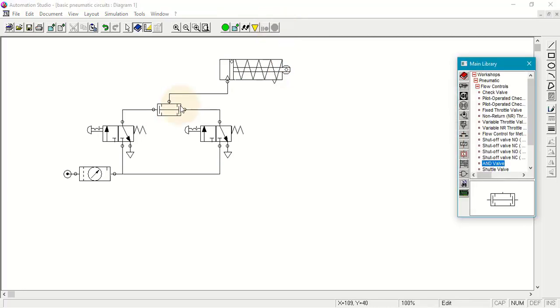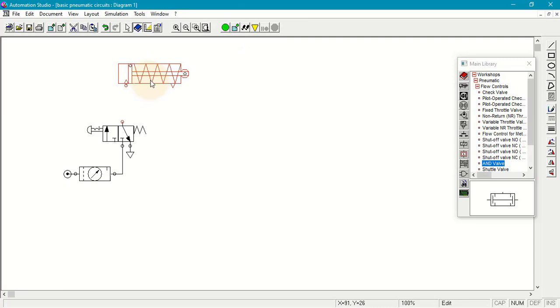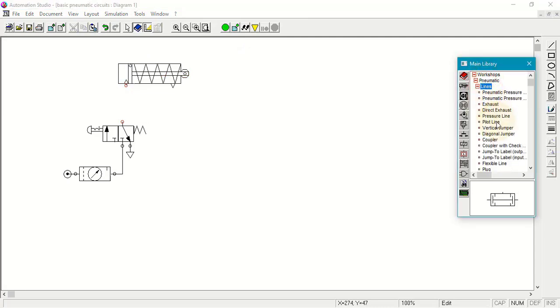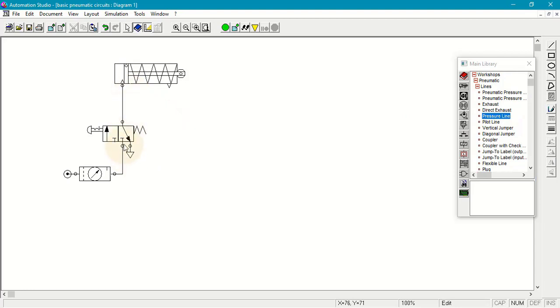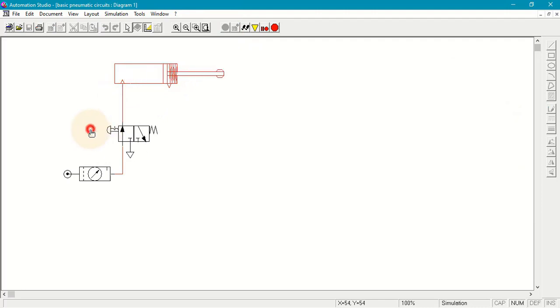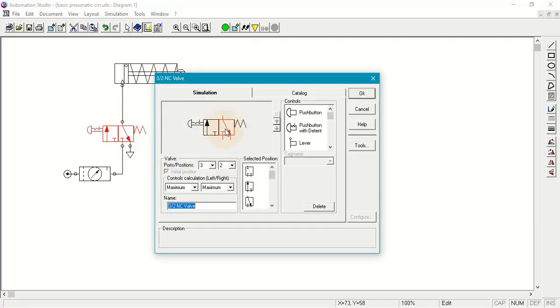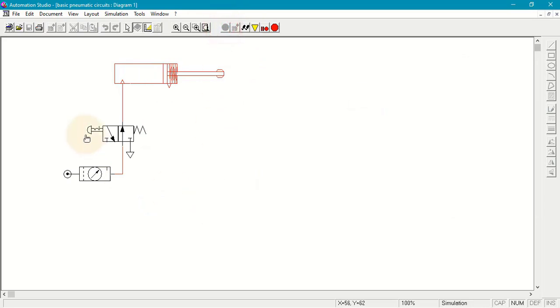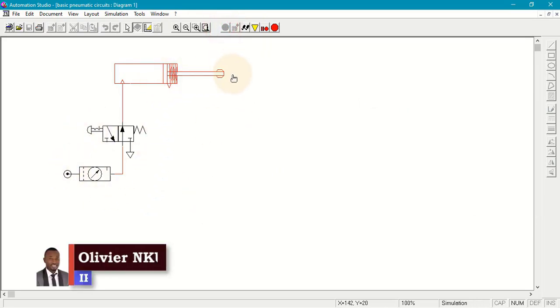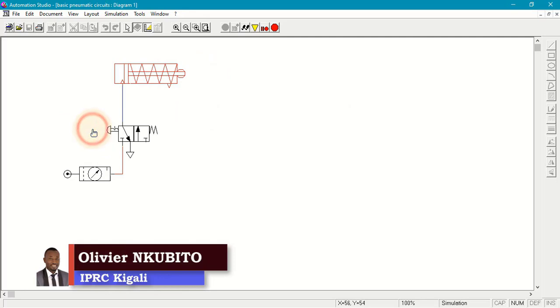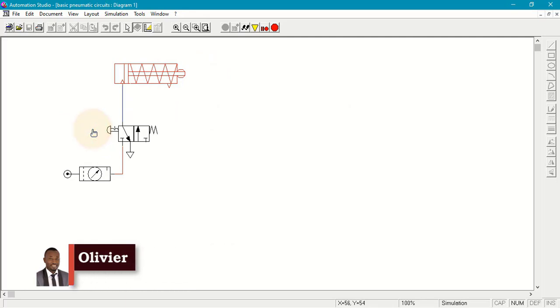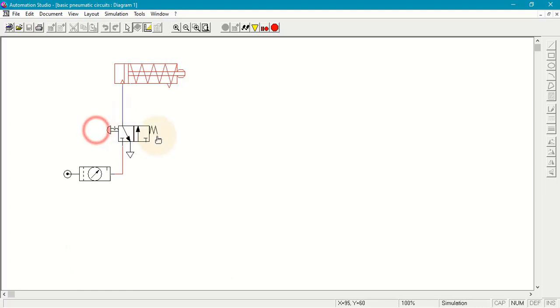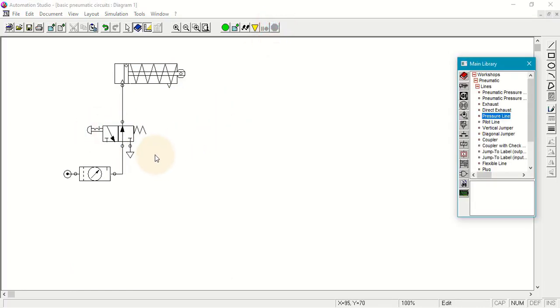What about NOT logic? This current setup is the YES logic, because when we use a normally closed DCV, you have to apply a signal for the cylinder to extend. We are going to change the DCV to be normally open. Now with no signal applied, the cylinder is extended — this is NOT logic. If we press the button, the cylinder returns back. That's the difference between NOT logic — using a normally open DCV — and YES logic.